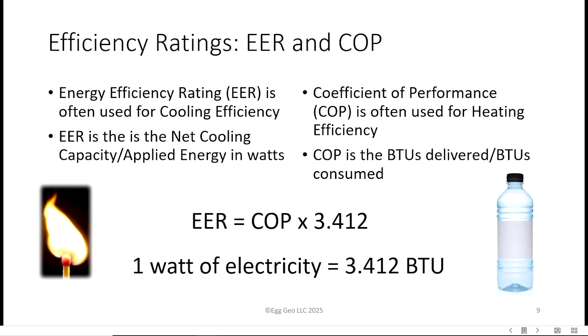With an electric heater, if you put 1 kilowatt in, you will get 1 kilowatt of heat, which is 3,412 BTUs of heat. If you put 1 kilowatt of electricity into a geothermal heat pump, that 1 kilowatt will run the compressor and the pumps on that heat pump, pick up 4 more units of heat out of the ground, and deliver 5 units of heat into the space, for a grand total of 17,000 BTUs of energy for 1 unit of electricity.